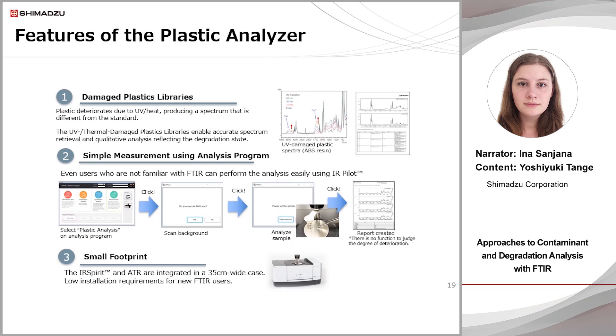Plastic Analyzer has three key features: highly accurate degradation libraries, simple measurement using an analysis program, and a small footprint. Spectra obtained by stepwise ultraviolet or thermal degradation of multiple types of plastics are recorded in these libraries, enabling highly accurate spectrum retrieval and qualitative analysis which reflects the degradation state. Simple measurement using IR pilot allows even users unfamiliar with FTIR to perform measurements and spectrum searches without inputting detailed conditions. Finally, with the compact FTIR IR Spirit and the ATR integrated into the sample chamber, the footprint of the instrument is the size of an A3 piece of paper.